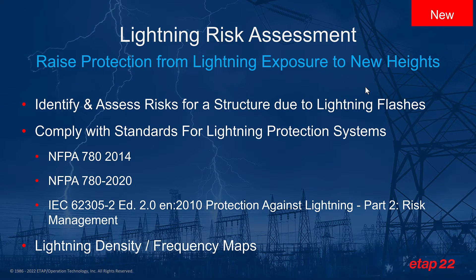Another new capability that we've added to our safety portfolio is lightning risk assessment. Lightning risk assessment allows us to raise the protection from lightning exposure to new heights, by identifying and assessing the risk for a given structure due to lightning flashes or lightning incidents that may happen around that area. The lightning risk assessment calculator allows us to comply with standards for lightning protection systems such as NFPA 780 2014 and 2020 standards, as well as IEC 62305 edition 2, which gives us the ability to define protection against lightning and do certain risk management.